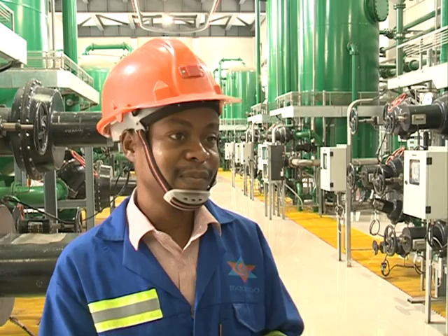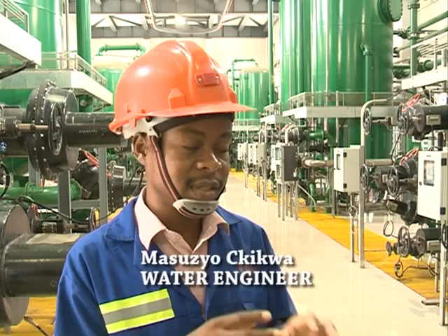This is the demineralizing section, part of the power plant system where we produce water for the production of steam. Our main aim here is to remove the scale-forming ions as well as suspended solids. This process starts with clarifying. After the clarifying, the water is pumped to the filters there. Those are dual-medium filters; there are two, where we remove the suspended solids.